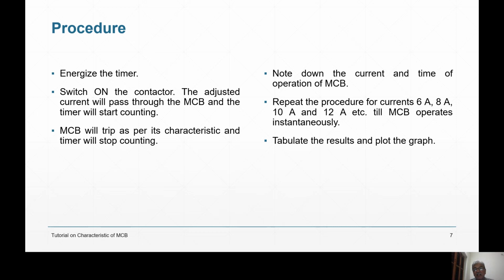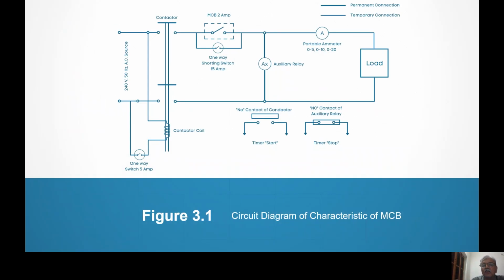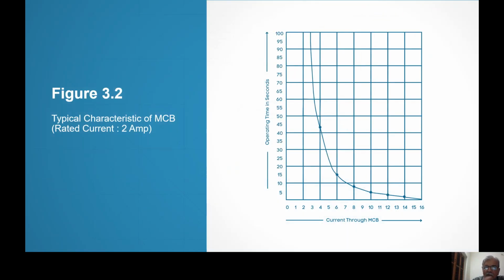Right? But the MCB will operate at some current instantaneously, say 12 ampere. Then taking a reading has no meaning, because instantaneously means you just make it on and off. Probably the timer will not be able to take the reading, because the timer is not meant to read 30 milliseconds or 40 milliseconds. It is measuring some seconds or some minutes. So take readings only up to instantaneous operation, and then tabulate the results and plot the graph, right? So this is what you have to do. This is what our business was: we are using the MCB, and then we plot the characteristic.